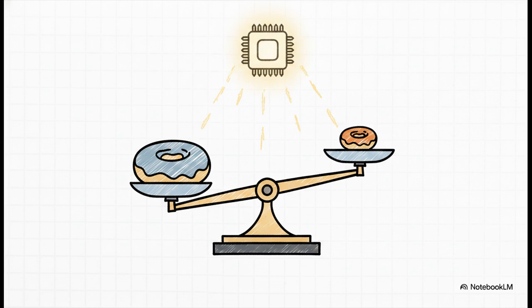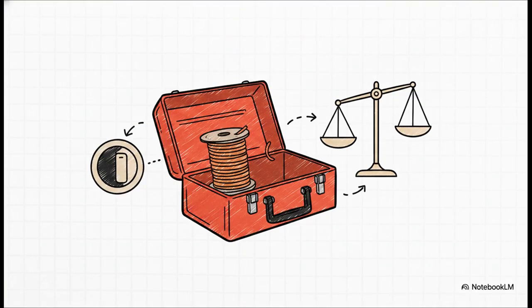It completely levels the playing field, making sure the relay isn't accidentally tricked into tripping just because the physical CTs on the high voltage and low voltage sides happen to be different sizes. Pretty brilliant, right? Okay, let's take a quick breath and summarize this new toolkit of yours. You now know exactly how to specify input settings for your analog signals. You can confidently justify your copper cable run choices based on the physics of burden. And you understand how the relay mathematically normalizes completely disparate signals using software, all to make those accurate split-second protection decisions.